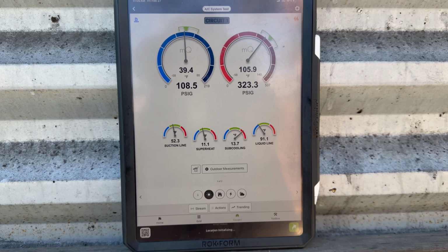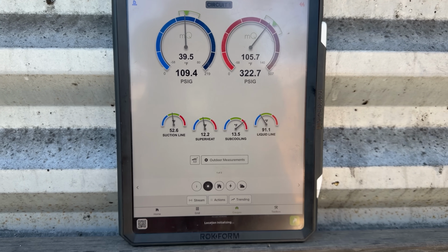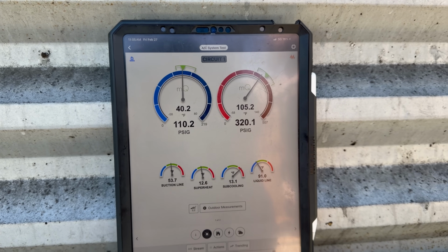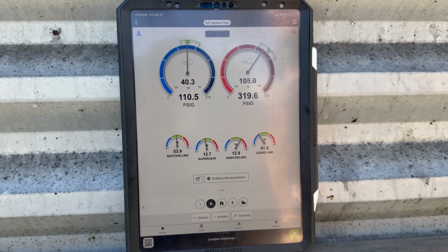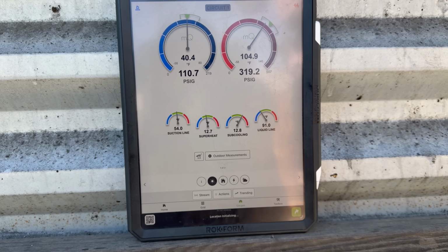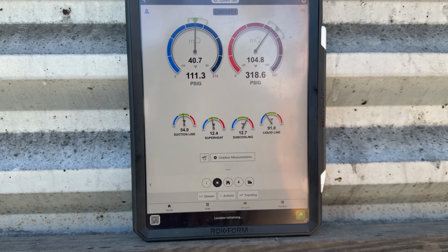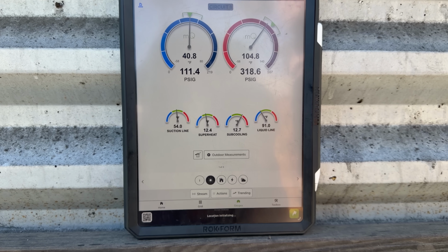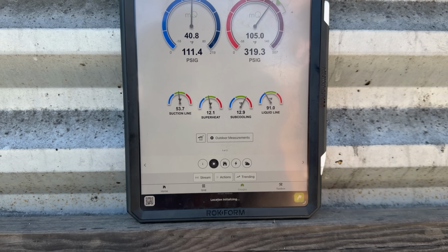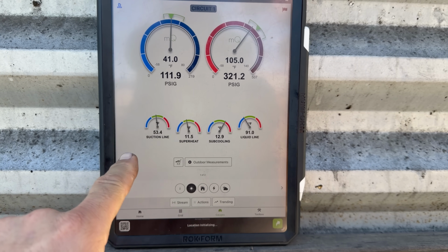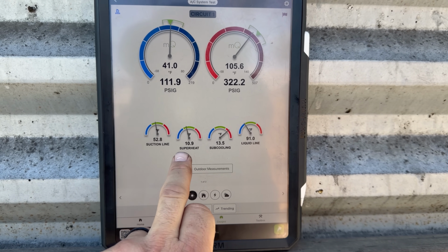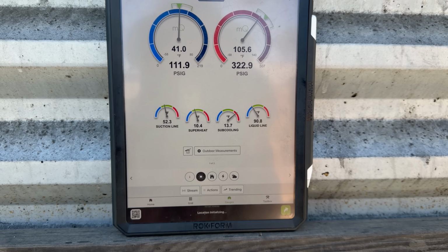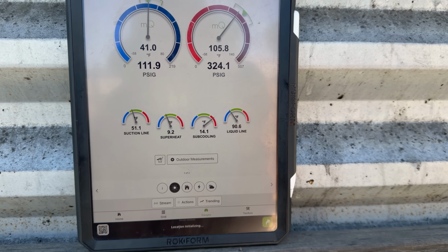All right, we are probed up. We are on the vitals screen. You can go through all sorts of measurements to see all sorts of things. This unit does not have liquid pressure ports, so our subcooling is going to be kind of skewed because it's using discharge pressure, and there's more than likely a pressure drop from discharge to liquid, but we don't know because I can't measure it. But judging by this, the expansion valve's doing its job maintaining superheat. The subcooling doesn't seem crazy.